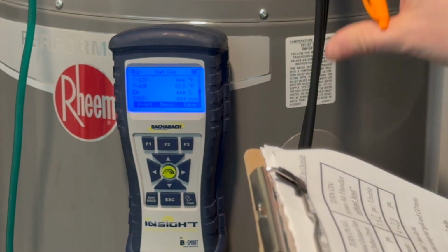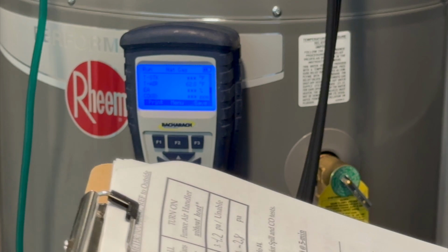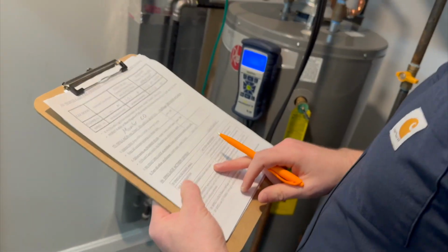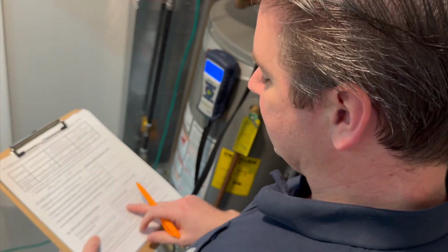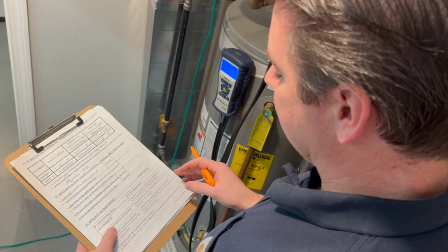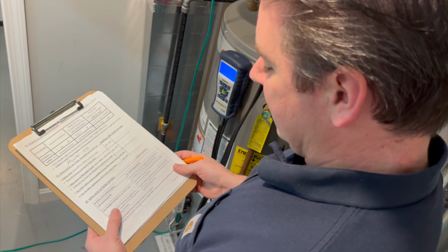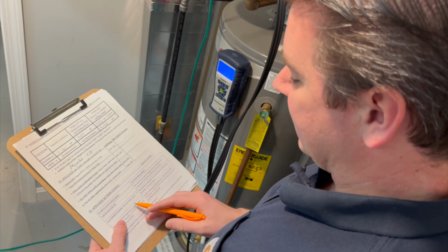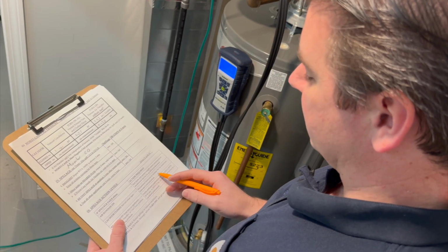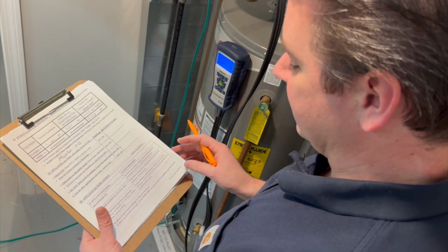While I'm waiting for that to do its thing, I'm going to go to spillage action levels down below. So if spillage fails when the air handler's on, we want to seal ducts, resolve supply and return imbalances, or recommend service by a qualified professional. If it fails when the CAZ door is closed but not when open, recommend measures to increase the air connection between the CAZ and the house.